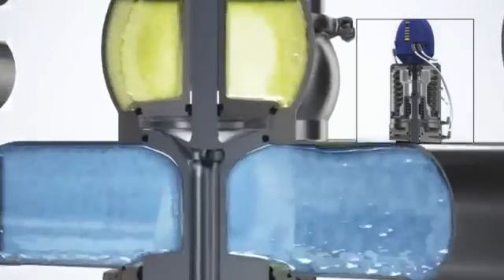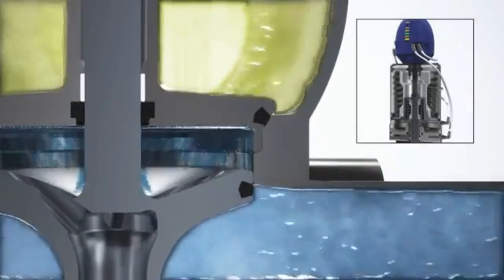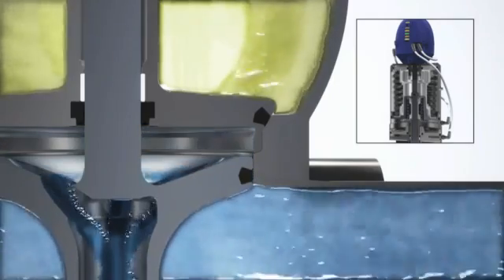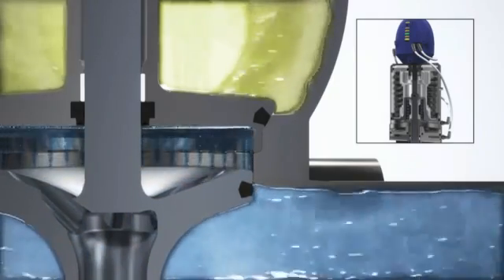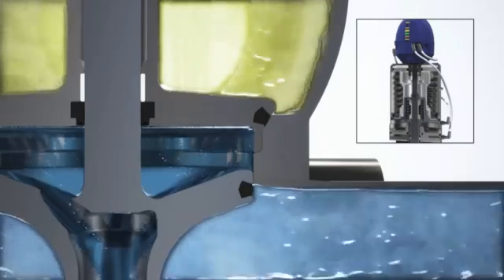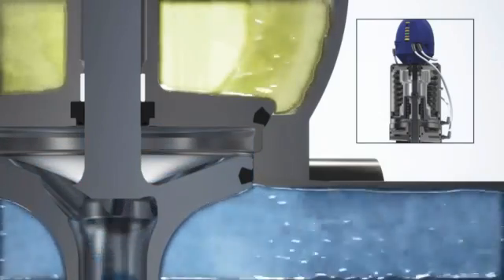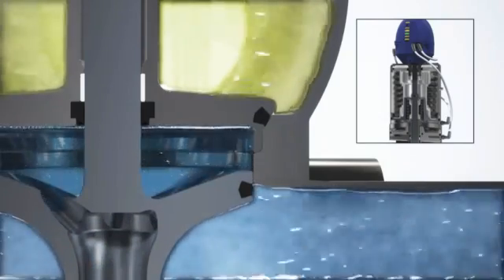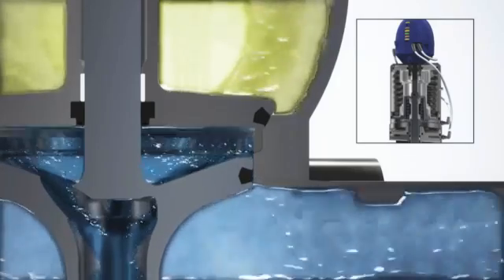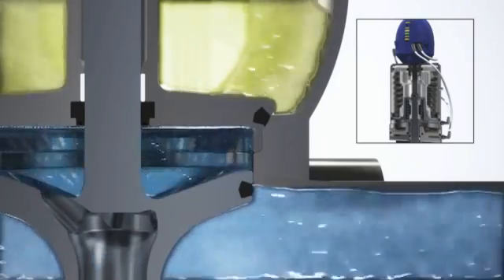Like the seat lift operation, the fast-acting seat push function is controlled by a defined metal-to-metal opening which provides a throttling edge. This speeds up the cleaning process by creating high turbulence and scrubbing effects, thereby making very efficient use of minimal CIP fluid.